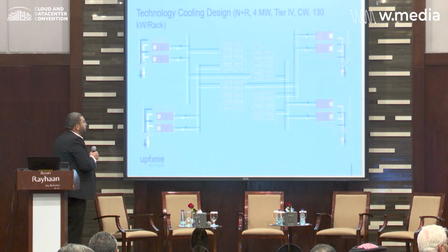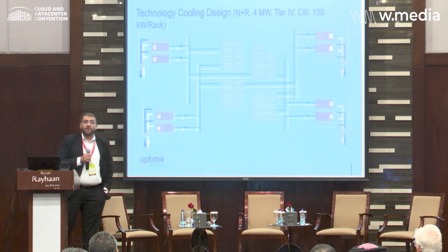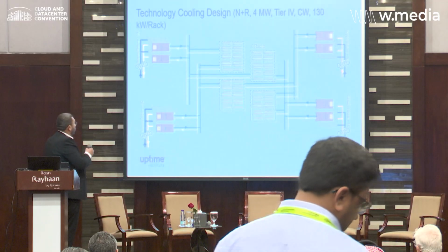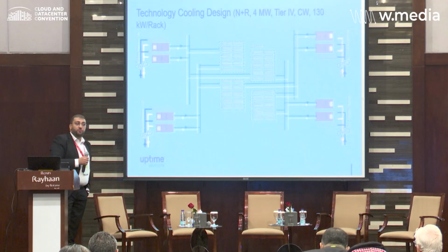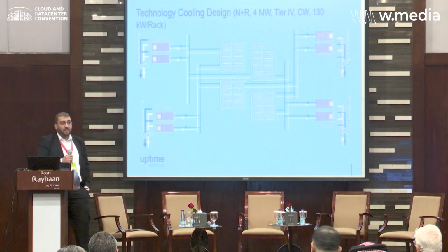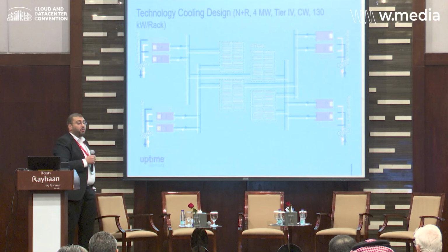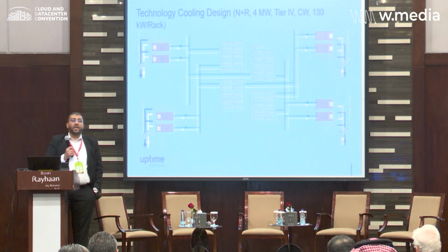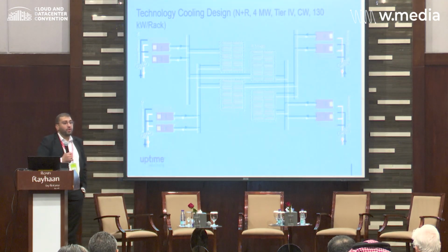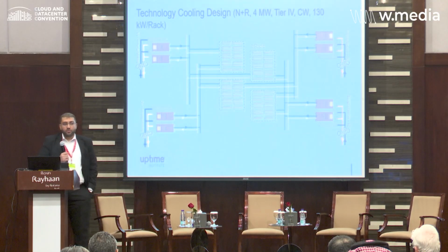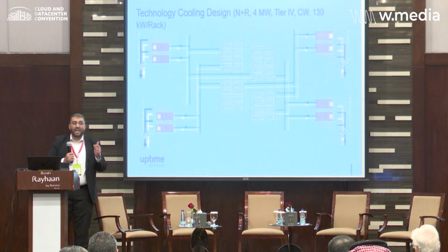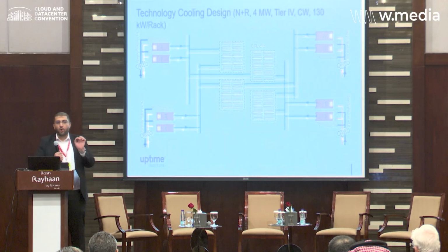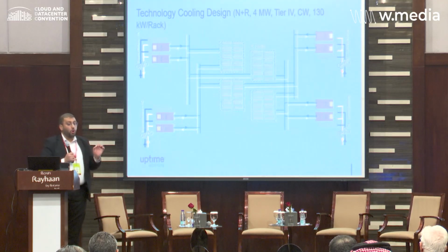Now let's have a look at the CDU. Similar to the configuration we saw in the chiller plant, we have a distributed redundant configuration. So as you can see, you have 4 paths, path A, path B, path C, path D, which is 4 to make 3. Any fault or leak in any of the primary side of the CDU, the secondary side of the CDU, or the tertiary side will not impact the cooling to your AI workload. Remember, the purpose is to first sustain the AI workload and to protect the valuable IT equipment, because a single leak or a major leak could really damage the IT equipment, the AI equipment, which is worth millions.